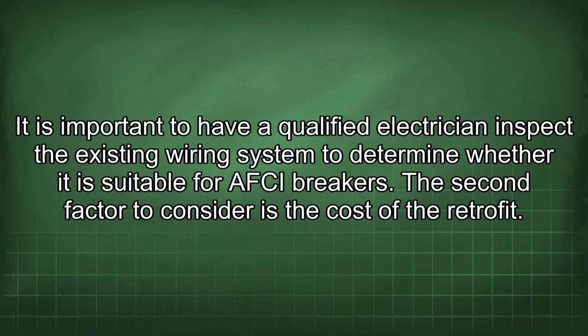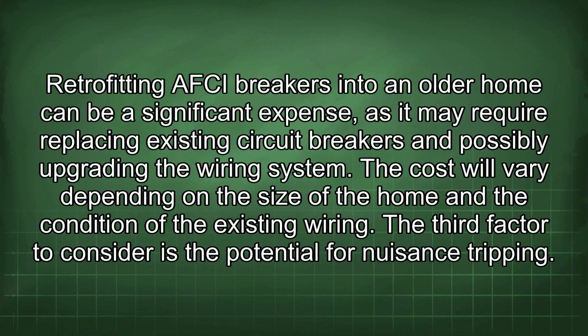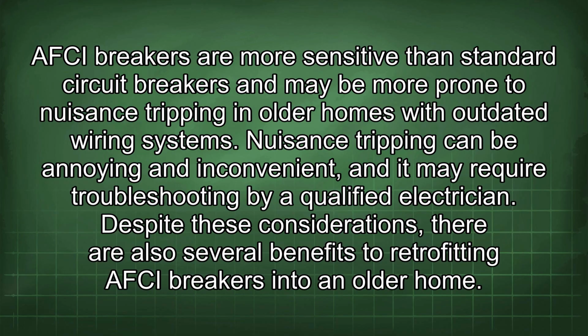AFCI breakers. The second factor to consider is the cost of the retrofit. Retrofitting AFCI breakers into an older home can be a significant expense, as it may require replacing existing circuit breakers and possibly upgrading the wiring system. The cost will vary depending on the size of the home and the condition of the existing wiring. The third factor to consider is the potential for nuisance tripping. AFCI breakers are more sensitive than standard circuit breakers and may be more prone to nuisance tripping in older homes with outdated wiring systems. Nuisance tripping can be annoying and inconvenient, and it may require troubleshooting by a qualified electrician.